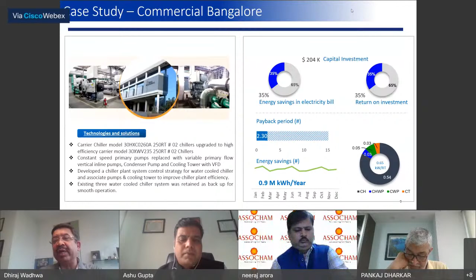The third case is a commercial application in Bangalore, with better weather conditions than NCR. Here we observed energy savings of around 35%, with return on investment close to 35% and an initial investment of $200,000. Importantly, we were again able to bring consumption down to about 0.63 to 0.64 kilowatt per ton, which should be the target. With all these initiatives and efforts, we clearly see the opportunities available, whether in the hospitality segment or any other.